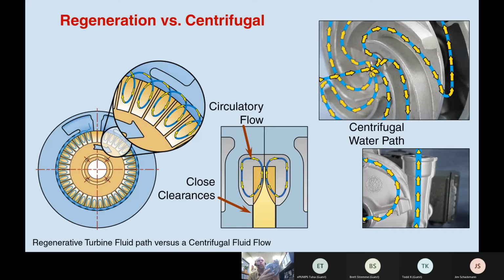centrifugal pump impeller. Now, the way a centrifugal pump impeller works is the water enters in through the center, and as the pump is rotating, the water goes along the vane, and then along the water channel and exits out the pump. So it gets one touch of the impeller vane and then leaves the pump. That's all it gets for touching the pump itself. Well, that doesn't build up much pressure, but it can build up flow. The bigger the impeller, the larger the flow.